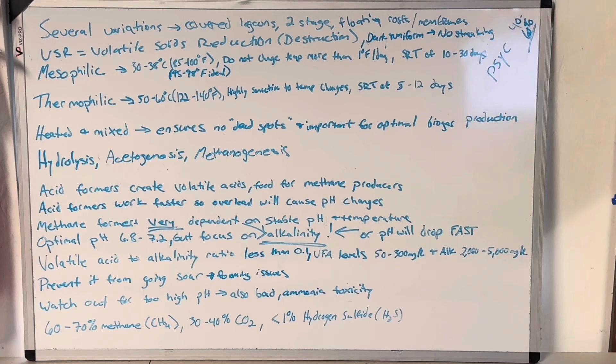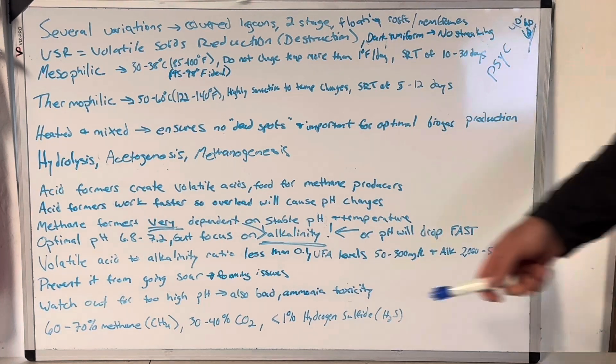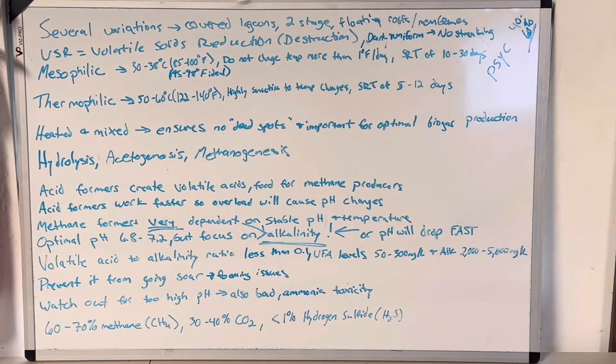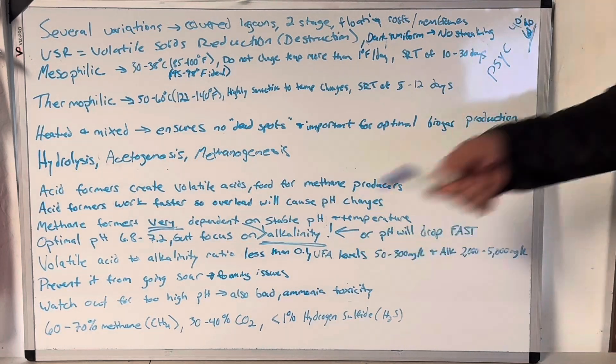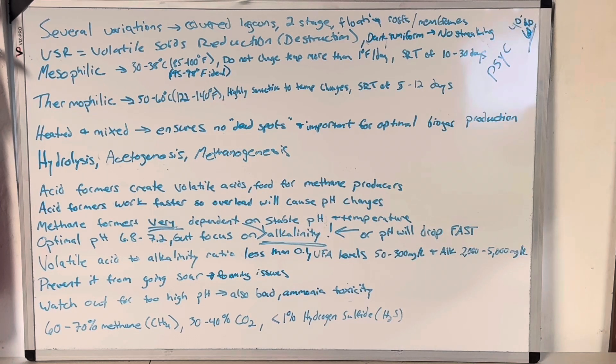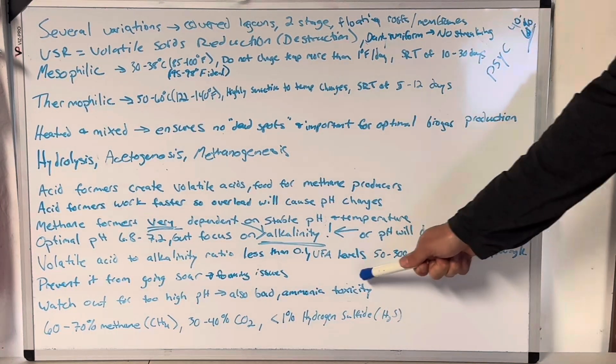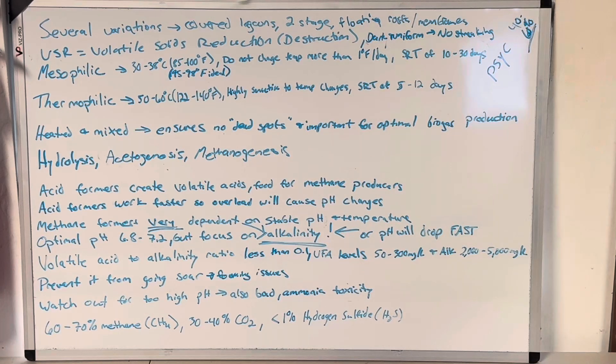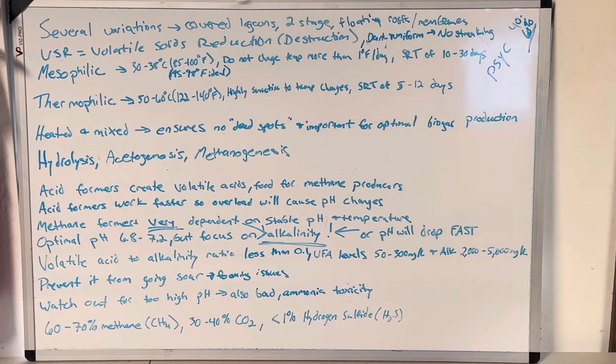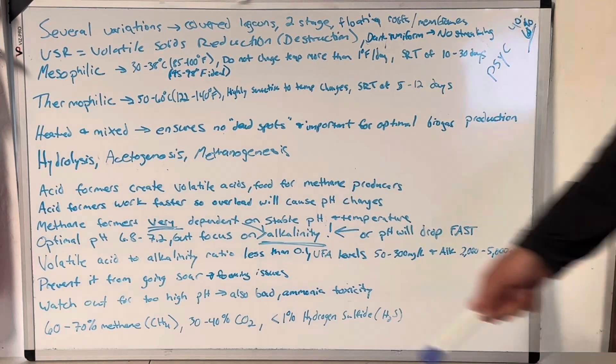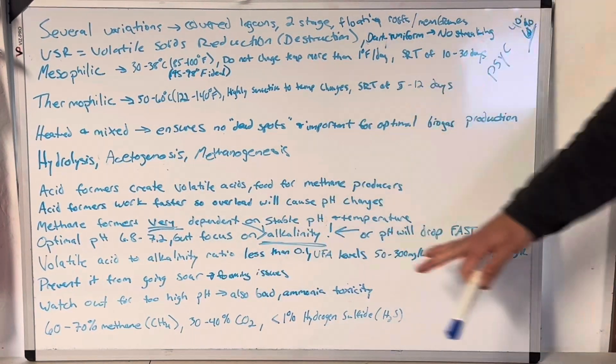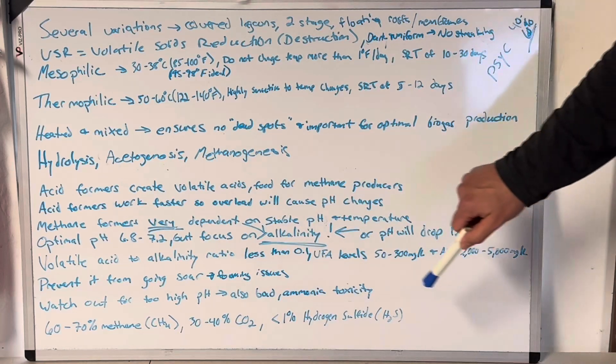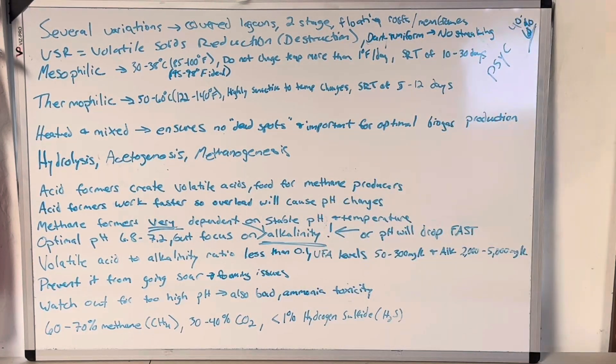So that's kind of the same thing here. Your volatile acid to alkalinity ratio should be less than 0.1. WEF study guide I read the other day said 0.1 to 0.35. I disagree with the 0.35. I think that seems a little high. From my experience, you want 10 times the alkalinity than the acid in the digester. You want a lot of runway on your buffer. Volatile fatty acid levels from 50 to 300 milligrams per liter and an alkalinity level of somewhere between 2000 and 5,000 milligrams per liter is good. This prevents it from going sour and inhibiting methane production, screwing up your gas ratios. And it also helps prevent foaming issues.